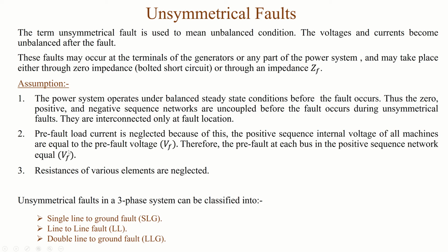So the pre-fault load current is neglected because of this. We are going to neglect the pre-fault current, and the positive sequence internal voltages of all machines are equal to the pre-fault voltages. So all the internal voltages are going to be equal to VF. The pre-fault voltage at each bus in the positive sequence network equals VF. All the resistance is going to be neglected. So I want to highlight this.